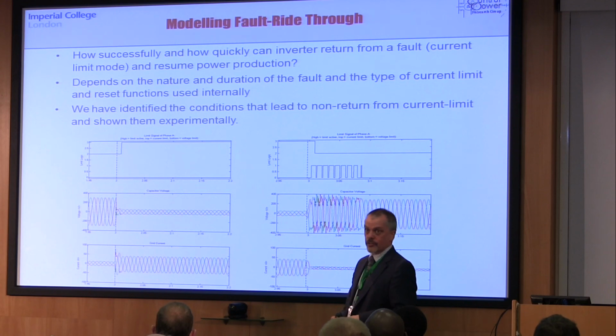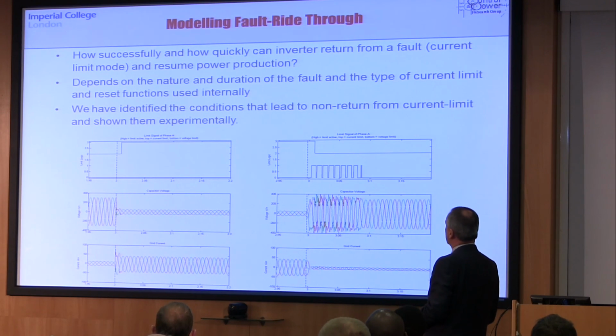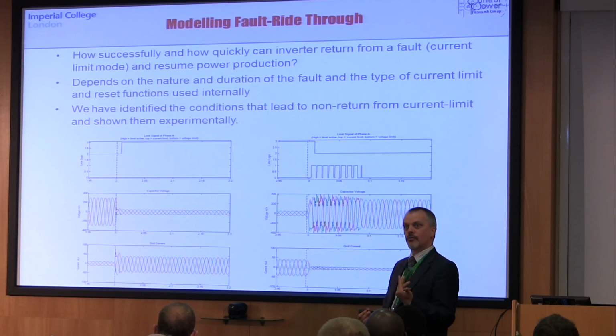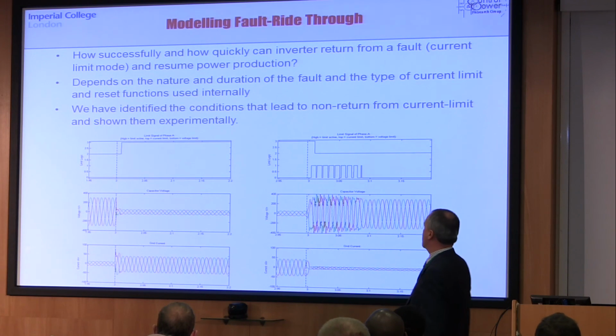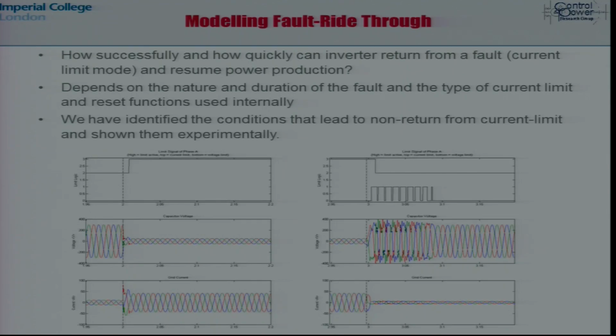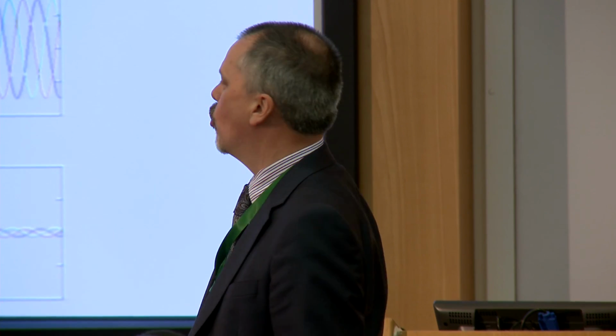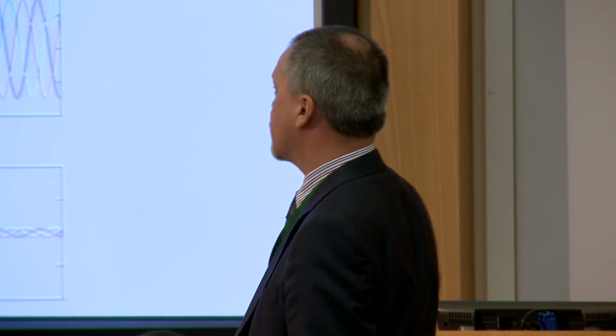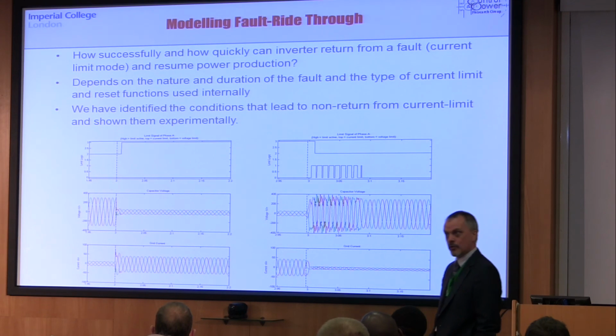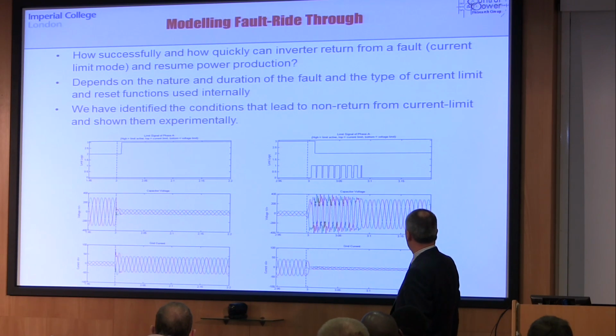Something similar, I think, applies to transient stability or fault ride-through. Do the converters come out of fault limiting in a sensible fashion, in a sensible time scale? And I think this is complicated because there are just so many ways of implementing current loops and current limiters and voltage limiters in converters. And it's hard for a network operator to be assured that the devices will come through a fault and be available again to supply power or to supply control services post-fault. And if they're not available post-fault, then there's a serious problem, clearly.